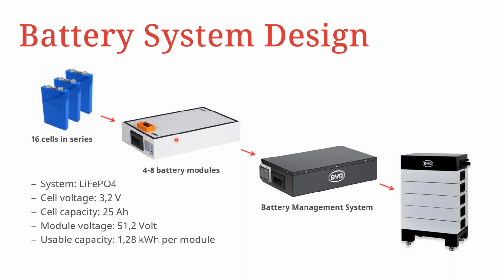Once you have the capacity in kilowatt hours per module, you'd stack these modules up to about 4 or 8, depending on your load or backup requirement, to give the total needed. A battery management system usually comes with the system to manage charging, discharging, and provide overcharging and over-discharging protection.